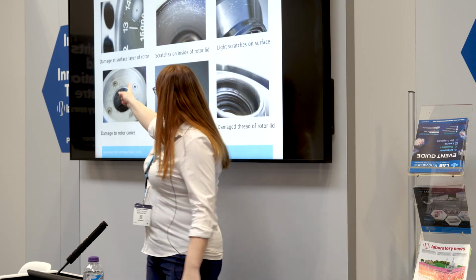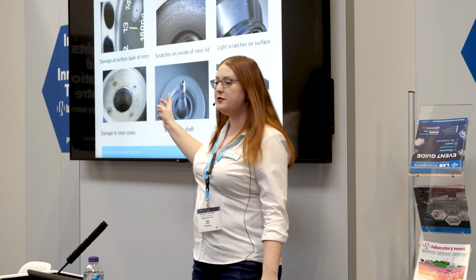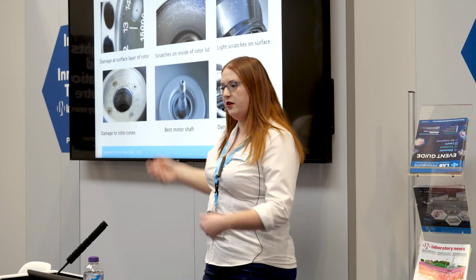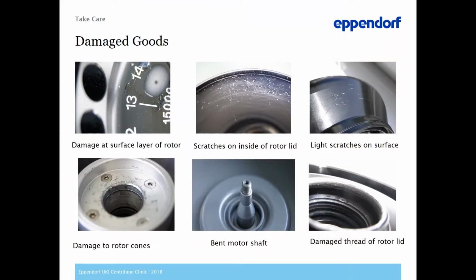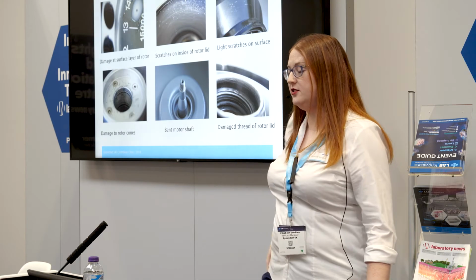We also get damage to the rotor cone and the motor shaft, where people don't put the rotors on properly, or they put them on a bit haphazardly. You get scratches, and this motor shaft is actually bent, though it's not very obvious in the picture. We also see where people haven't greased the thread on the rotor lid, so it's just metal grinding on metal. All of these things are making your centrifuge not safe.